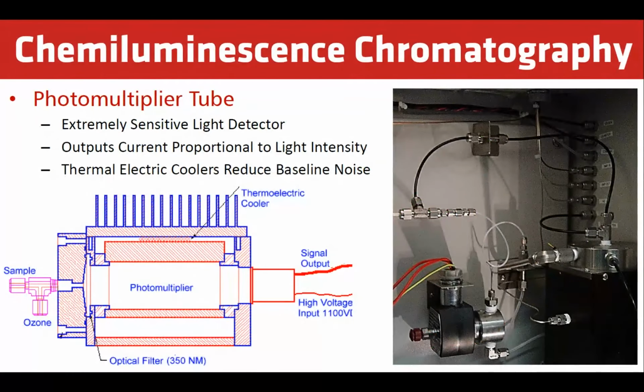The photomultiplier tube is an extremely sensitive light detector. The output current is proportional to the light intensity. We use thermoelectric coolers to reduce the baseline noise. Keeping the PMT at a lower temperature reduces baseline noise. To the right, you can actually see the PMT. The unit itself is mounted on the wall there on the right, and that's where the chemiluminescence happens in that upper chamber of the reaction cell.